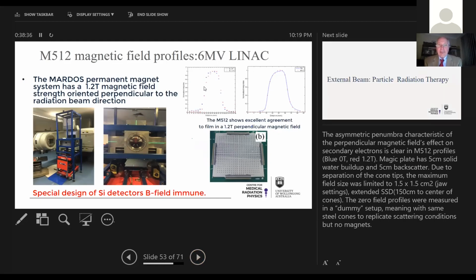You can see here in blue the profile of a 1 centimeter field without magnetic field, but when you apply the magnetic field, you are changing the penumbra and the distribution is no longer symmetrical. But the two-dimensional detectors which we developed do not use any ferromagnetic material like nickel, and they work beautifully and in full agreement with Gafchromic film. You can see here the detector profile that we are measuring in a 1.2 Tesla field. You see, it's not symmetrical, but it's exactly the same as measured by Gafchromic film, which demands 24 hours for obtaining a result. But here we're getting the result in real time, immediately. So now it's implemented in practice in the Elekta MRI LINAC, and we're working with this detector.